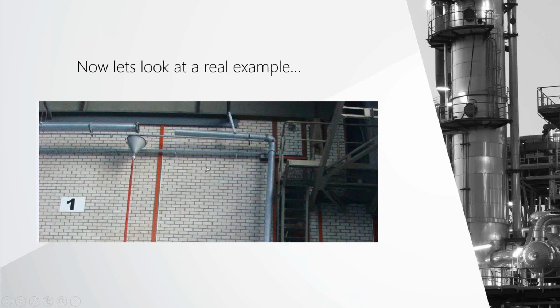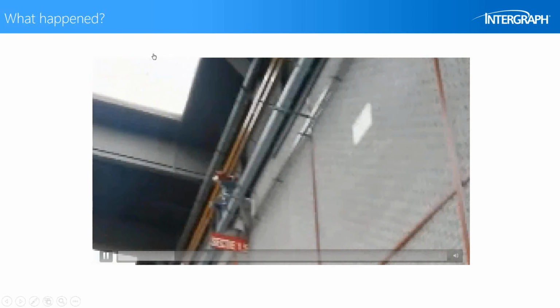Well, let's first of all look at it actually occurring, because due to some videos that were taken during the test procedure, we actually managed to capture when it failed. I apologize for the quality of the video, given the video was not set up to record the failure. What you see, the pipe is running across the top from the almost vertical through the screen, and you're seeing there the explosion as the coupling fails and the water is spraying out of the system.